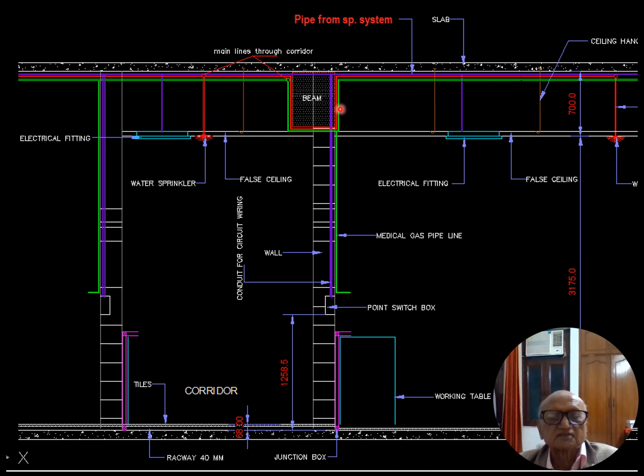So air conditioning ducts travel like this horizontally on both sides of the beam, and it may be in the corridor portion also. Now if this hank is more than 0.85, then you are supposed to provide a sprinkler on both sides. This is the sprinkler for sprinkling water in the area, but you are supposed to provide another sprinkler just at the mirror image here to take care of any fire within this hank area. The fourth item, I have not shown any false floor.